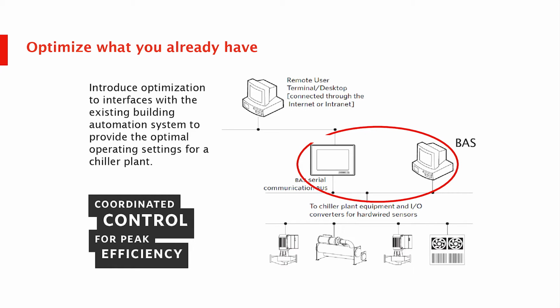So I talked a bit about optimizing what you have. Optimization is, how many people in the room golf? Okay, some. So the analogy might make sense. Optimization is kind of like getting a really good caddy. If you have a BAS system, everything looks like either a driver or a 5-iron. So having a good caddy, if you're on a hole and you pull out your 5-iron, because that's your standard club for this, it's 165 yards downhill. It's 165 yards, that's the only thing you're looking at. But if it's 165 downhill with the wind at your back, and on the other side of the green is a nasty pond, maybe you want something else.